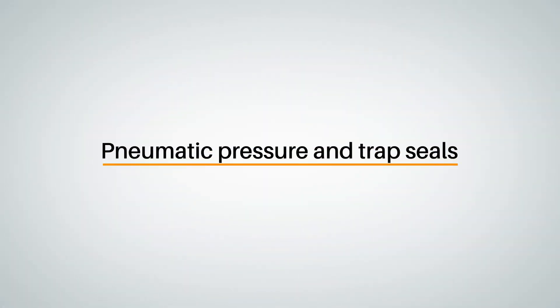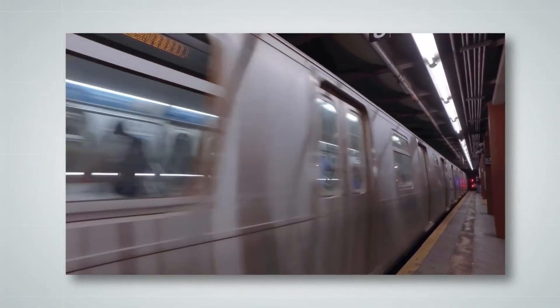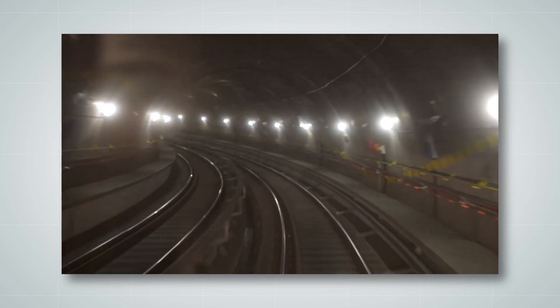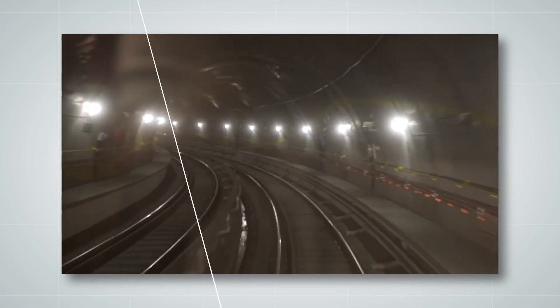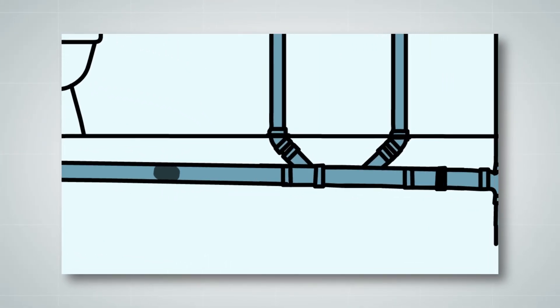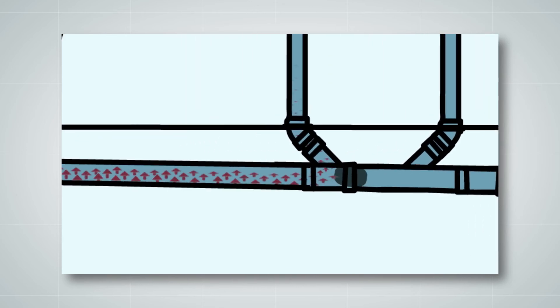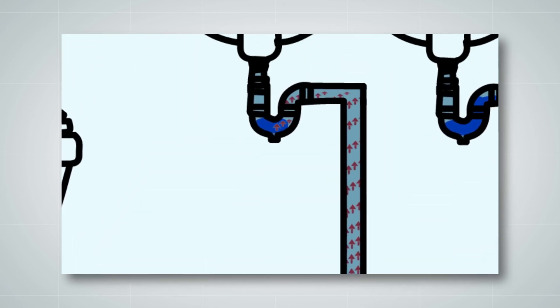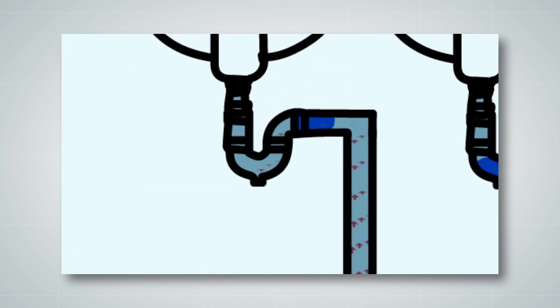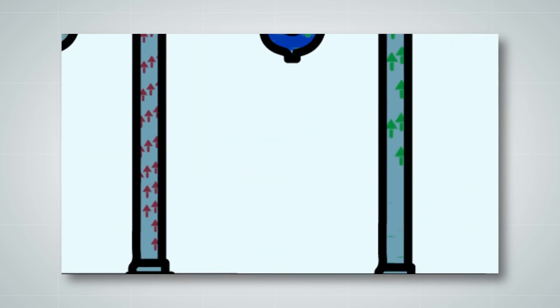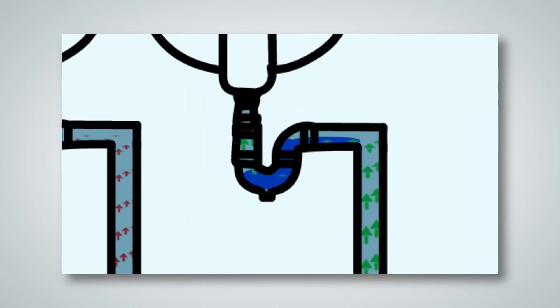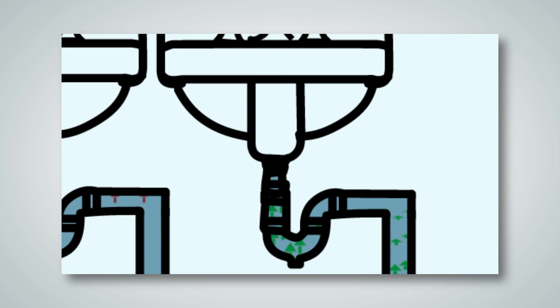In order to understand the effect of pneumatic pressure on a trap seal, think of a subway moving rapidly through a tunnel, pushing the air in front of the train so as to increase positive pressure ahead of the train, while sucking air from behind the train, causing negative pressure in that part of the tunnel. Effluent flowing rapidly down horizontal sanitary drainage piping can create enough negative pressure behind the flow to draw the trap seal water away from the trap, and can create enough positive pressure ahead of the flow to push any effluent present between the trap seal and horizontal piping back into the fixture.